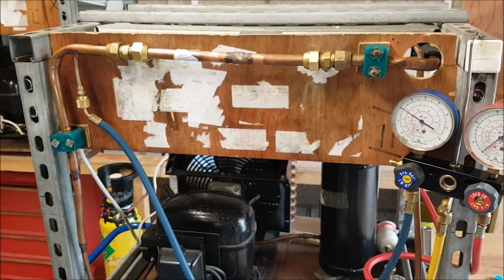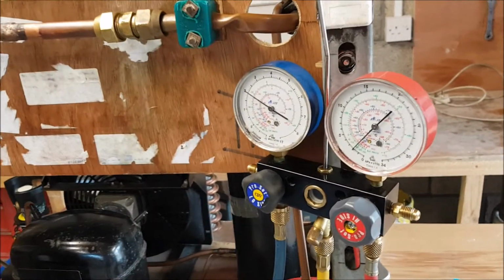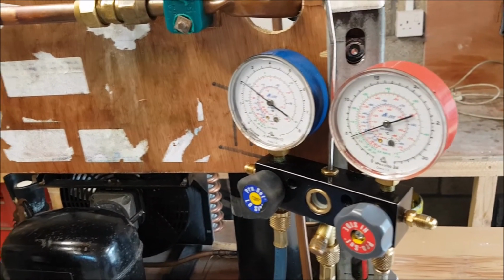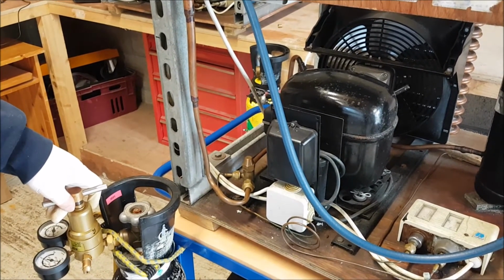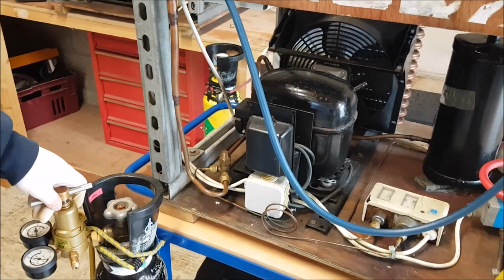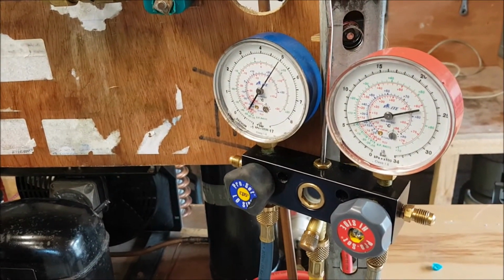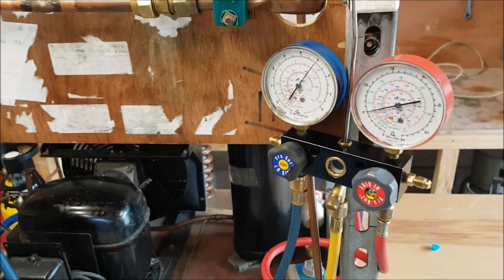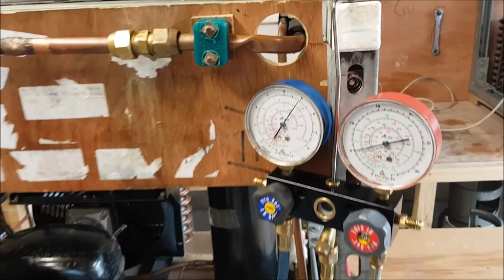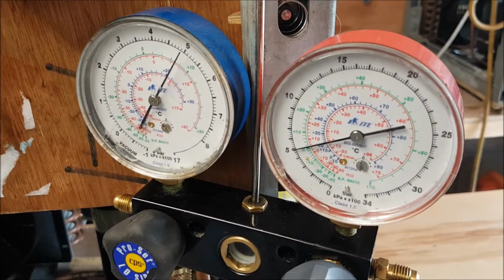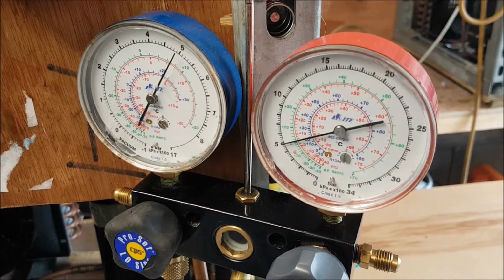Okay, so 2 bar pressure, you satisfy yourself, then once you've checked it at 2 bar pressure, you can maybe bring it up to about 5 bar pressure, which again is safe. So I'm just bringing it in. You can see it here on the actual gauge coming up. There we are at just above 5 bar pressure. Go through the same system again. Standing pressure, if you remember, on this was about 9.5, 10 bar. So eventually we would bring this up to the standing pressure of about 9.5, 10 bar.